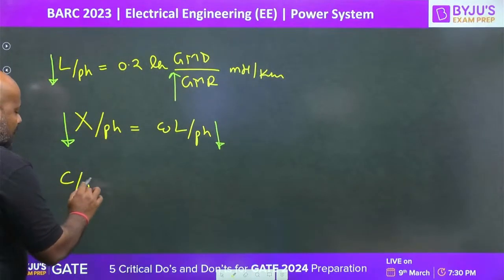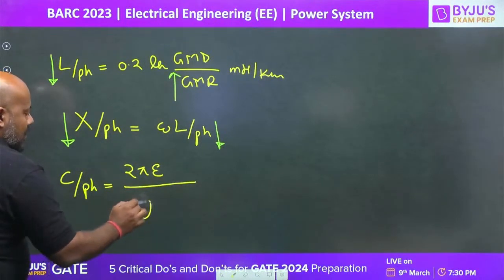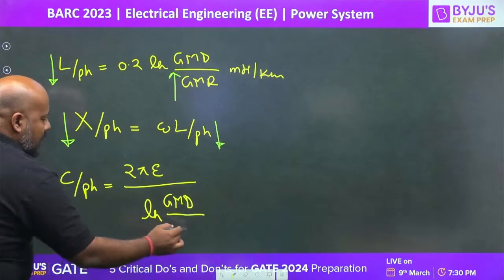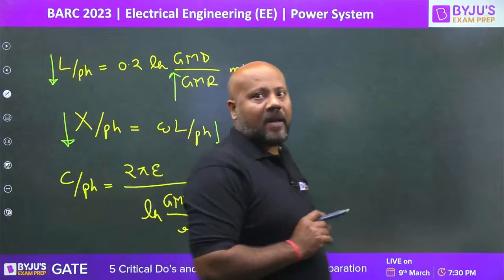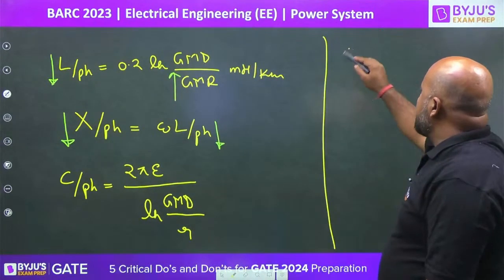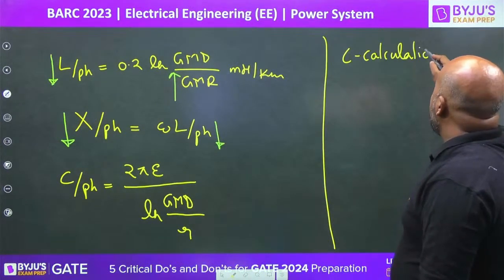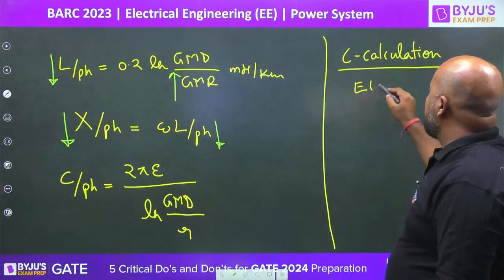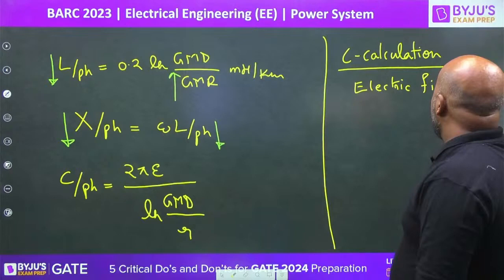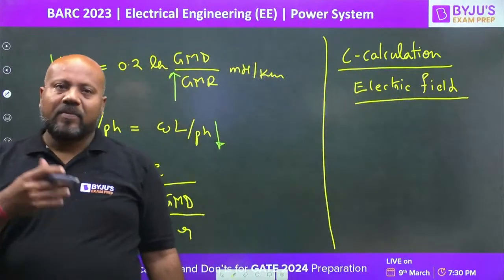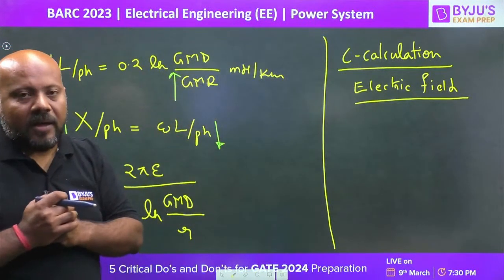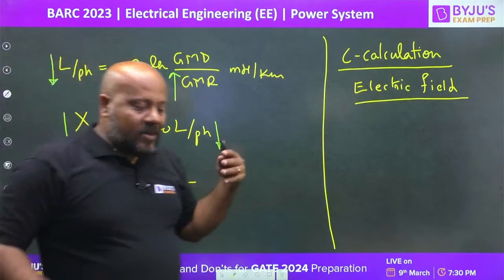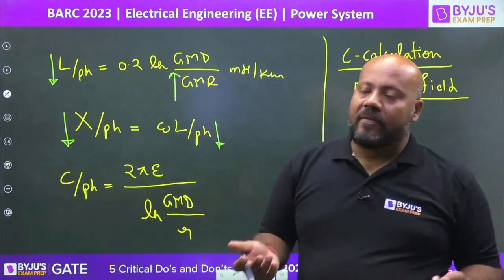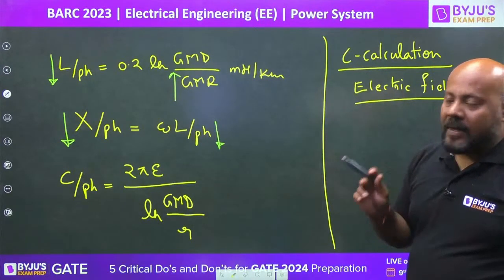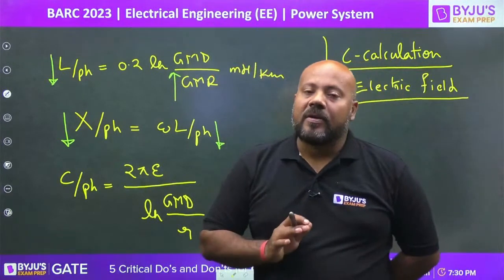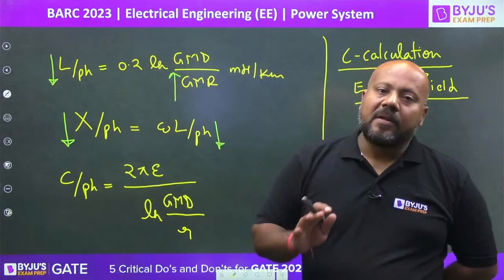What is going to happen with the capacitance? It is given as 2 pi epsilon ln(GMD/R). Now, I am not writing GMR. Why? Let me tell you. In case of capacitance calculation, we are dealing with electric field, and electric field cannot be present inside the conductor. Magnetic field can be present inside the conductor, but electric field cannot. It means when we are doing the capacitance calculation, there is no point of discussion for the internal flux - there is no internal flux. So the GMR concept you are using is applicable actually for the inductance calculation, not for the capacitance calculation. Technically speaking, for capacitance calculation, the GMR concept is not applicable.